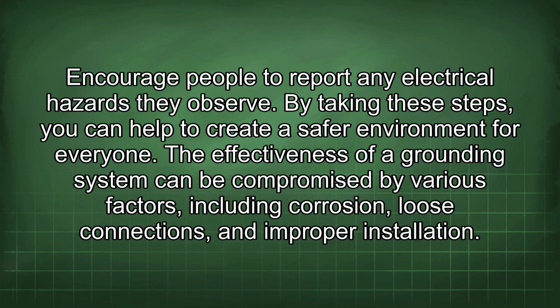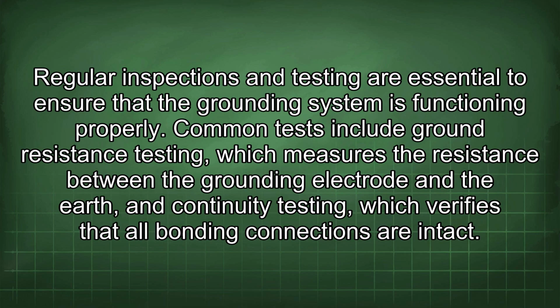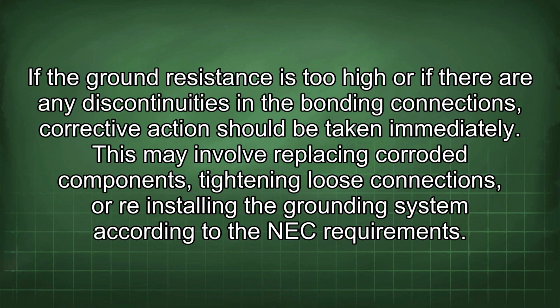The effectiveness of a grounding system can be compromised by various factors, including corrosion, loose connections, and improper installation. Regular inspections and testing are essential to ensure that the grounding system is functioning properly. Common tests include ground resistance testing, which measures the resistance between the grounding electrode and the earth, and continuity testing, which verifies that all bonding connections are intact. If the ground resistance is too high or if there are any discontinuities in the bonding connections, corrective action should be taken immediately.